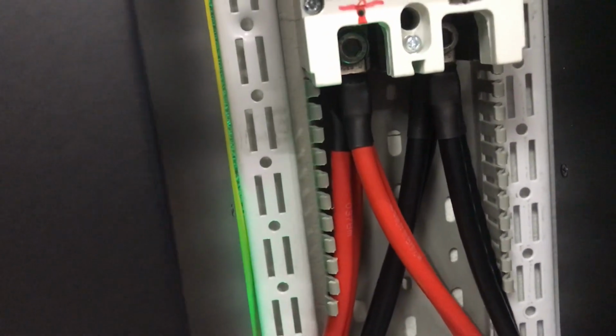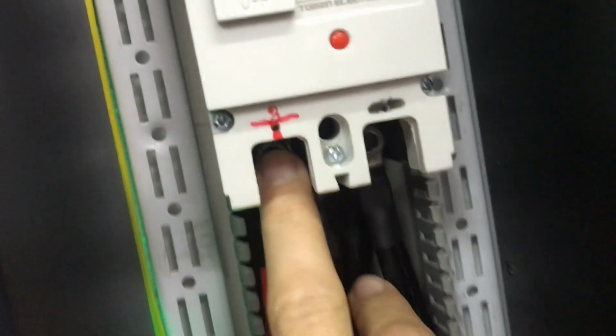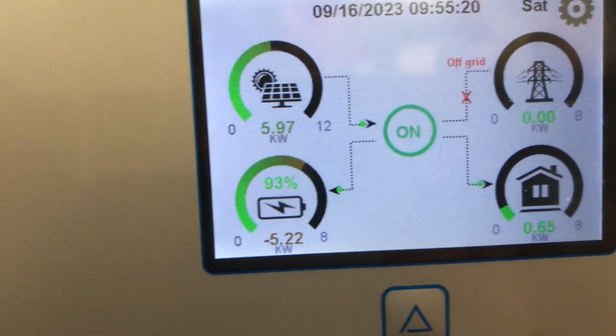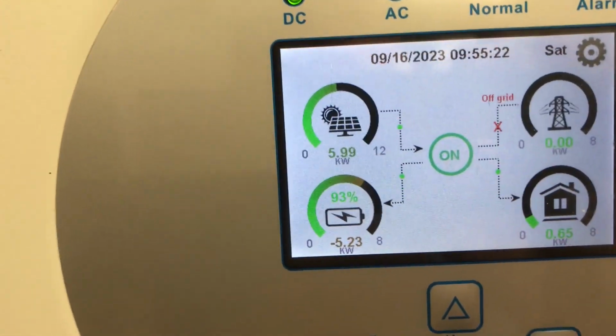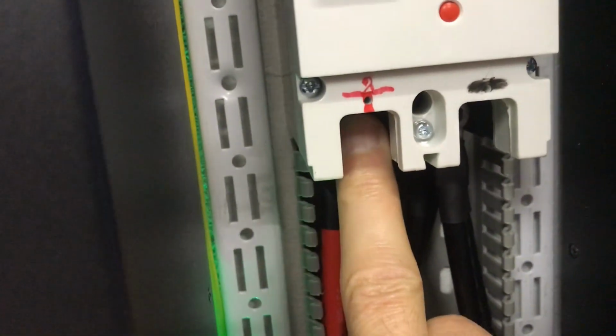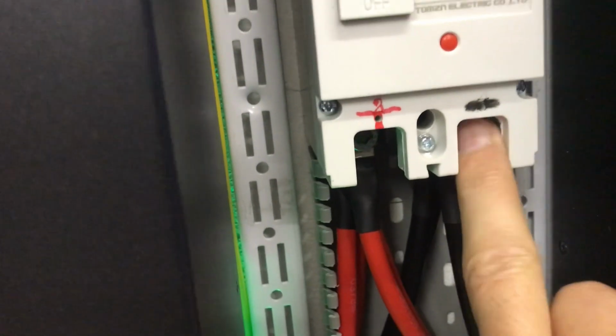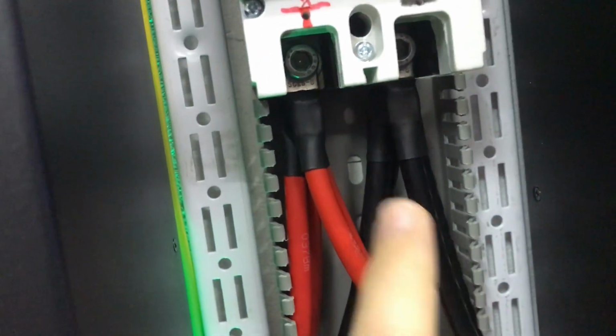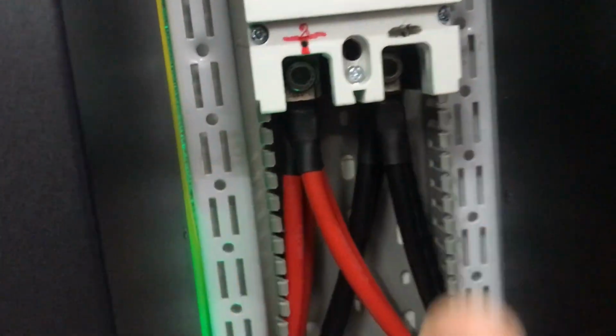Now, as with most electrical stuff, connections can be problematic because that's potentially where your highest resistance resides. So what I've done is, this is currently running at, I think, up to 5 kilowatts that it's charging at. So that's around about 100 amps that's currently coursing through these wires, and these terminals are cool to the touch. I've done this before as well, I just checked. These things are pretty much at room temperature, which is kind of just a rough guide to check whether I've got any issues with connections over here.